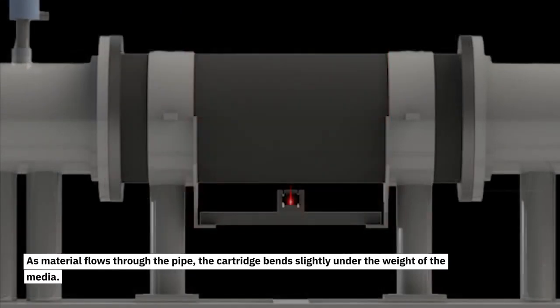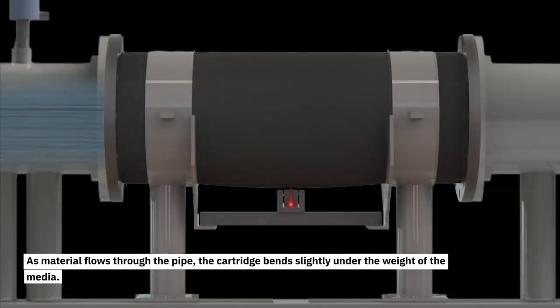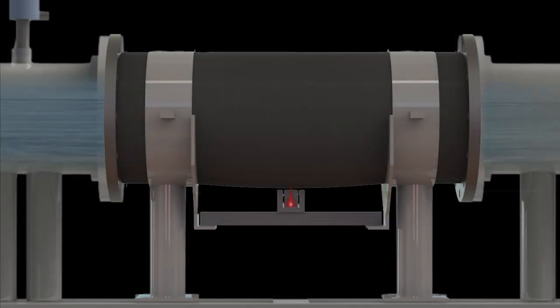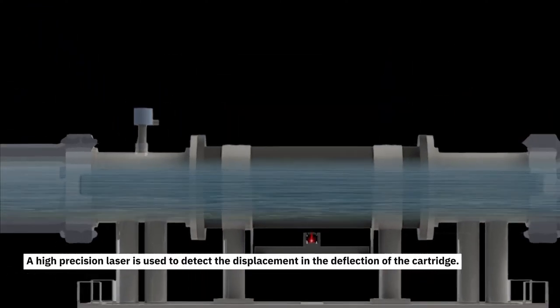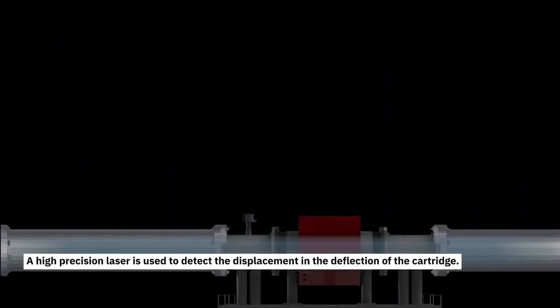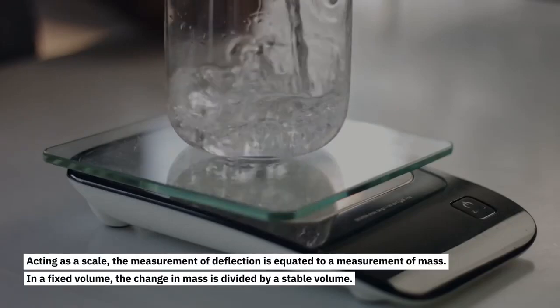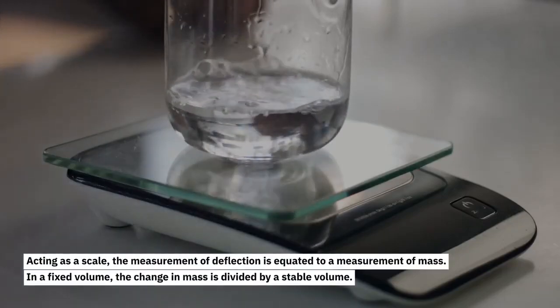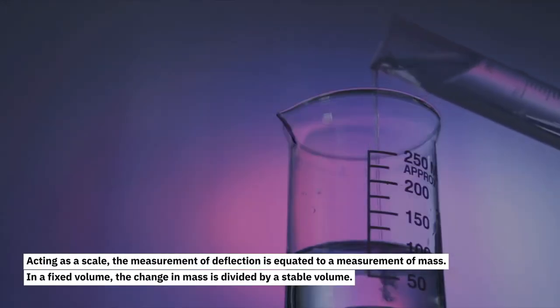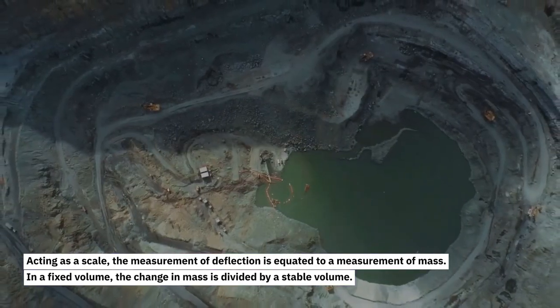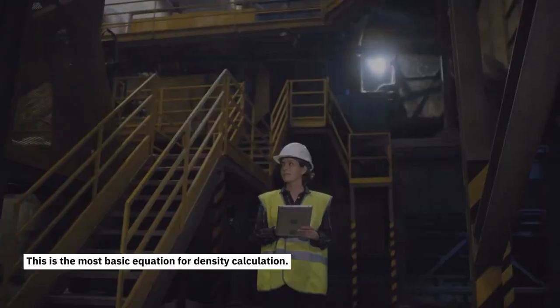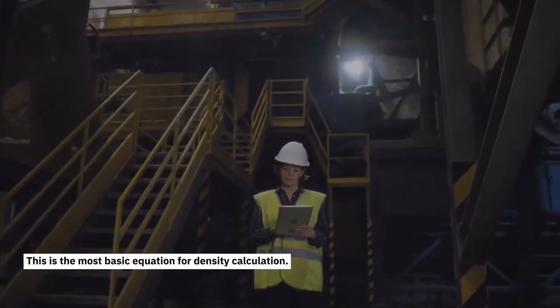As material flows through the pipe, the cartridge bends slightly under the weight of the media. A high-precision laser is used to detect the displacement and the deflection of the cartridge. Acting as a scale, the measurement of deflection is equated to a measurement of mass. In a fixed volume, the change in mass is divided by a stable volume. This is the most basic equation for density calculation.